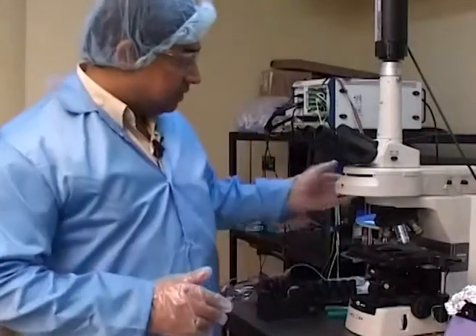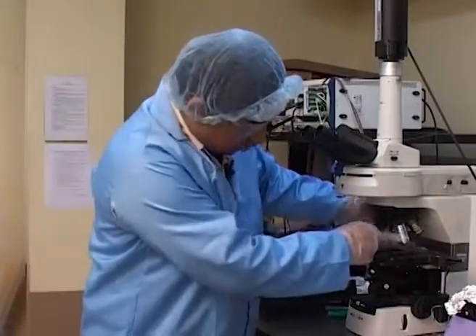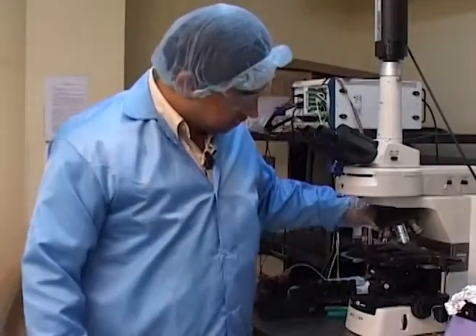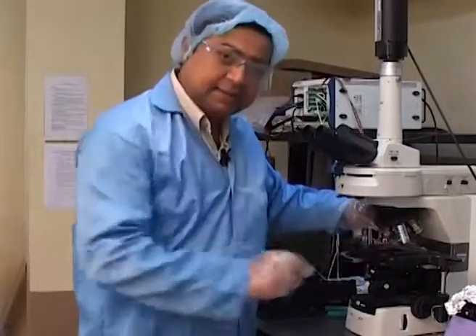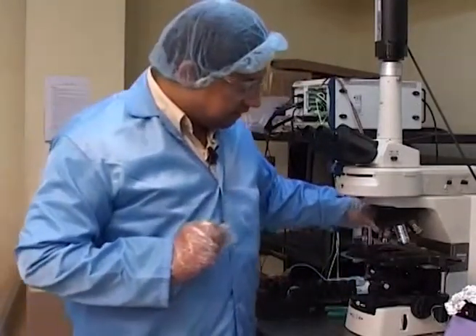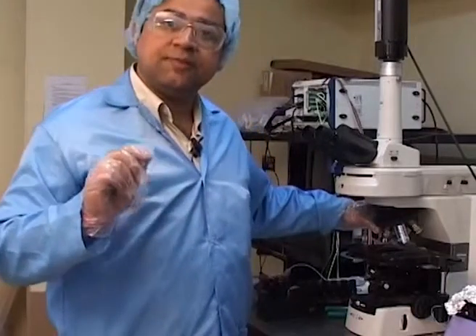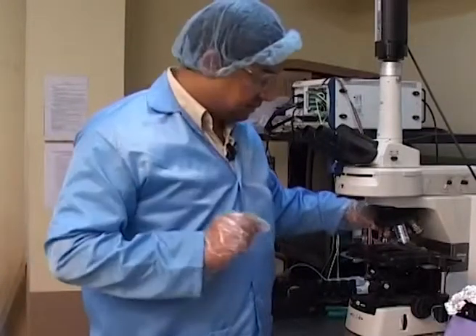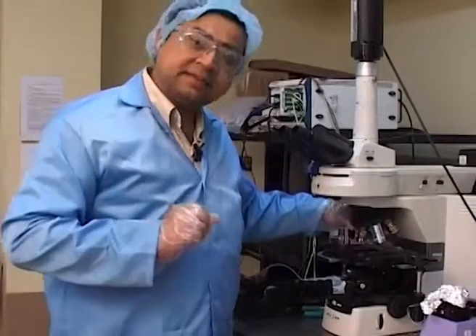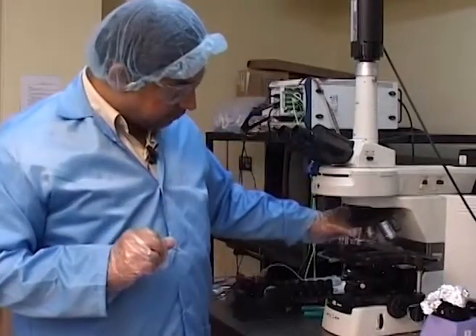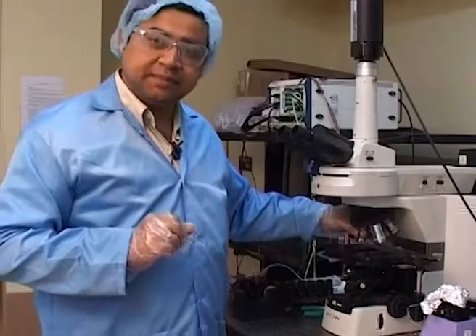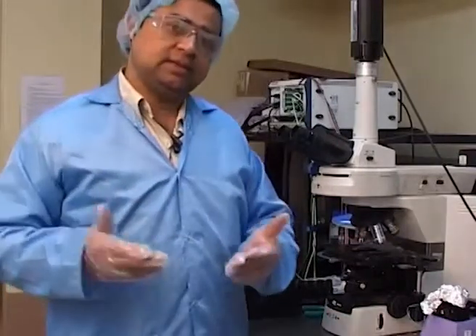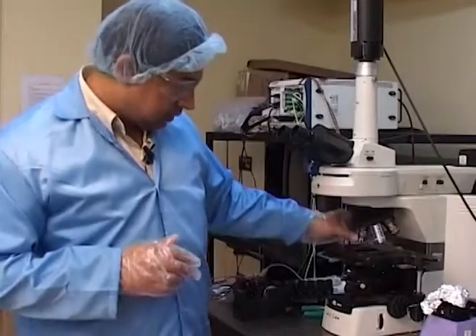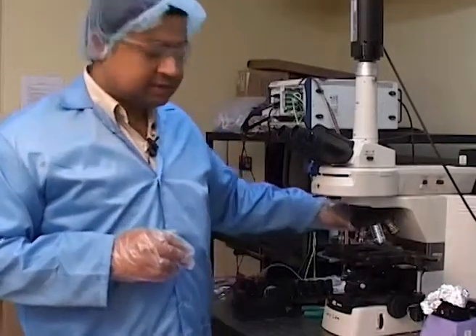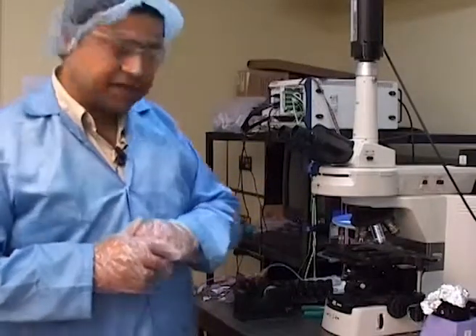Here in this particular zone, these are also known as the objectives. Essentially they are nothing but lenses, and they all have the capability of magnifying in different capacities. So we do have objectives varying from 4x, which means that the image seen through the microscope is 4 times the actual size of the object, all the way to about 150x. Essentially there are about 6 objectives here.